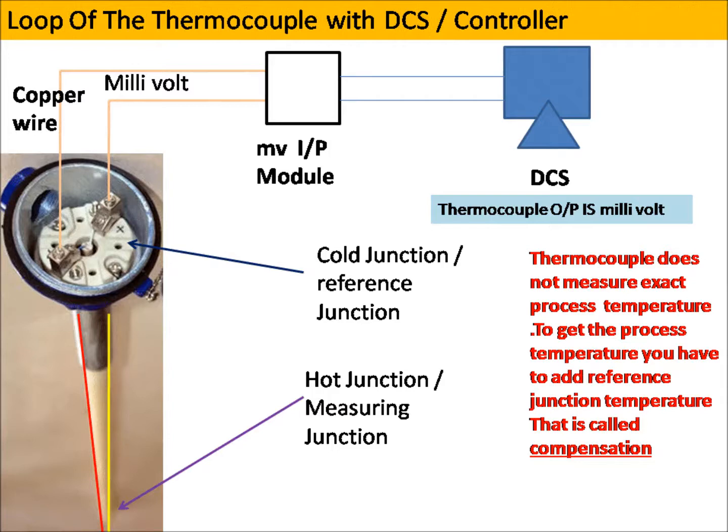As mentioned, the thermocouple does not measure the exact process temperature — it measures the temperature difference between the exact temperature minus the reference temperature, which is ambient temperature. To get the exact process temperature, you must add the ambient temperature. This is called compensation. The voltage generated by a thermocouple is a function of the temperature difference between the measurement and reference junctions.